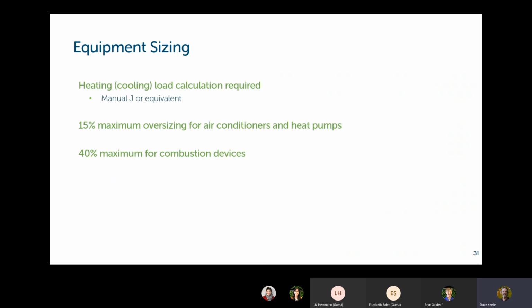Anecdotally, it's not at all uncommon. In fact, it is very common in Vermont to find brand new houses with boilers that are literally twice as big as they need to be. And it's not all that unusual to find boilers that are 3 times as big as they need to be. So often this has an efficiency impact. For some things like air conditioners, it also has a performance impact. They actually work worse when they're bigger than they're supposed to be. And of course, it has an economic impact on the front end, because the bigger the systems are, the more they cost the homeowner.